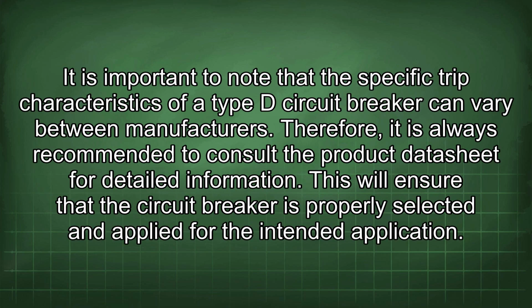It is important to note that the specific trip characteristics of a Type D circuit breaker can vary between manufacturers. Therefore, it is always recommended to consult the product datasheet for detailed information. This will ensure that the circuit breaker is properly selected and applied for the intended application.